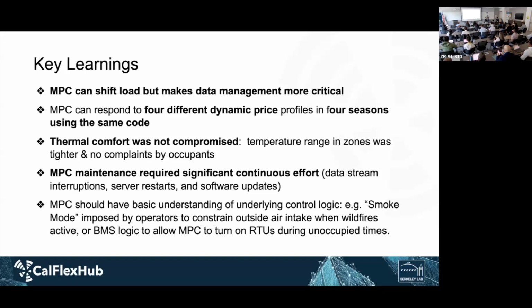In the end, we implemented a slight change to the MPC, which was actually pretty easy, where we told it: you cannot use outside air anymore, you have to recirculate the air. It definitely adjusted the targets, and it was still able to save with respect to the baseline. But having solid communication with the facility managers, checking the alarms of the buildings, and being integrated with the overall communication infrastructure of the building is pretty important for a robust implementation of MPC.